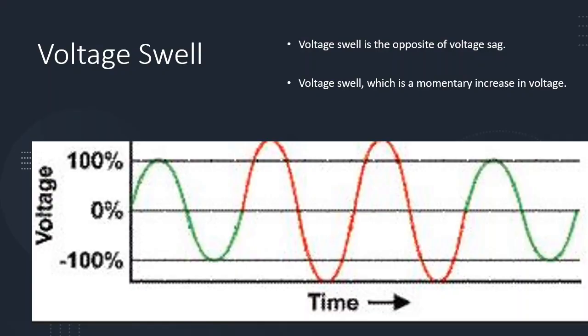What is voltage swell? It's the complete opposite of voltage sag. Voltage sag was a drop in the nominal voltage values, while voltage swell is a momentary increase in the voltage values — like an expansion or explosion of the voltage. The duration is similar: from a few cycles to a few seconds, less than a minute. The voltage exceeds the nominal value beyond 100%, crossing the voltage limit, and this can be from 10% to 90% above nominal, or 0.1 to 0.9 per unit above nominal.